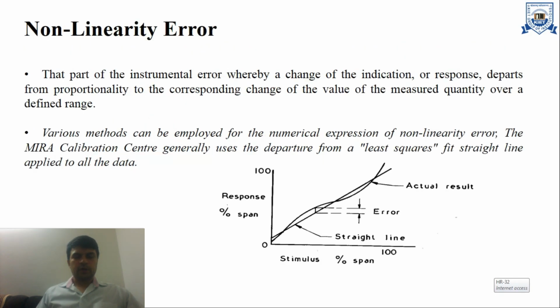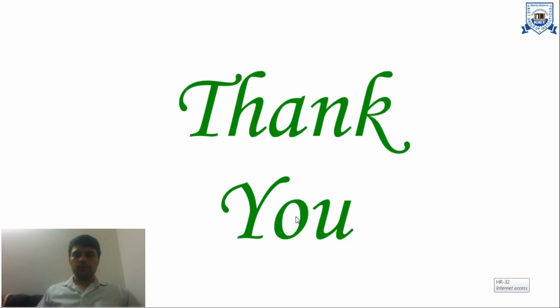Then non-linearity error. This is that part of instrumental error where a change of the indication or response departs from proportionality to the corresponding change of the value of the measured quantity over a defined range. Various methods can be employed for numerical expression of non-linearity error. The MIRA calibration center generally uses the departure from a least square fit straight line applied to all the data. In this case, we have the response and my span in percentage, and here is my stimulus. This is my actual measured data, and I draw a straight line, and according to this I find the non-linearity in my system. This is all about my lecture.